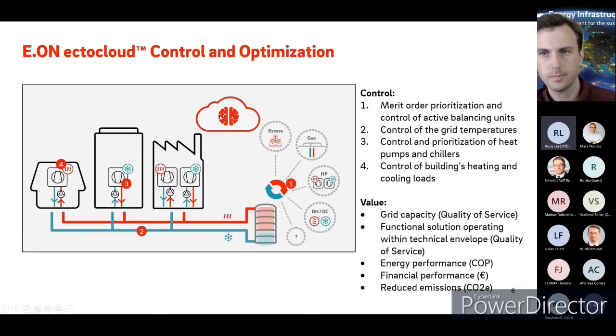The type of control that we do through EctoCloud is really optimizing the merit order of which type of waste heat or centralized balancing heating or cooling that we need to put into the system, so that we use the most efficient energy sources at the right time, and also are able to use the accumulator to store in advance based on forecasted consumption.